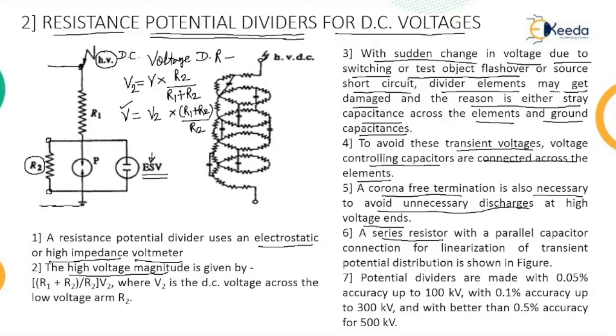A series resistor with a parallel capacitor connection for linearization of transient potential distribution is also shown in the figure. This figure shows the connection of the resistance and capacitor. Whenever there is a flashover or short-circuit, that can be avoided by using a protective device placed in the circuit. This protective device forms a spark gap, which is sufficient to protect the electrostatic voltmeter connected in the circuit.